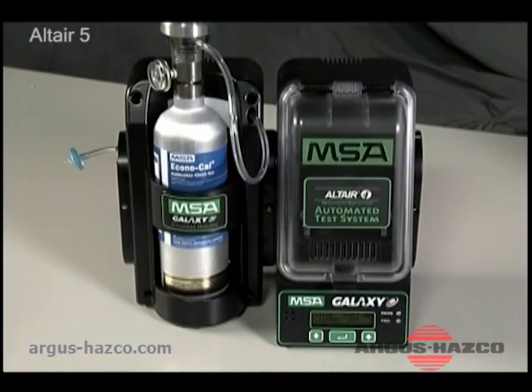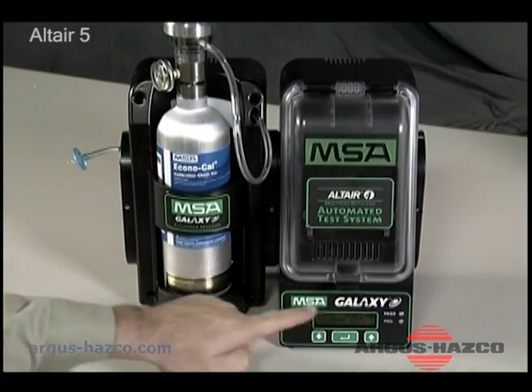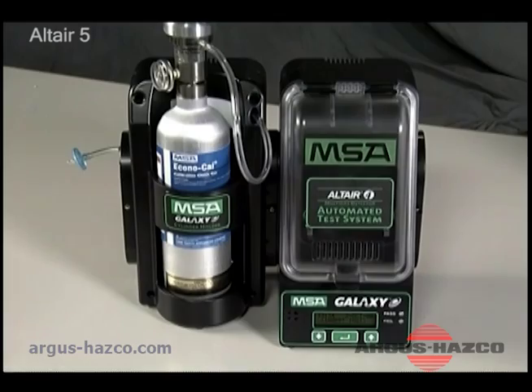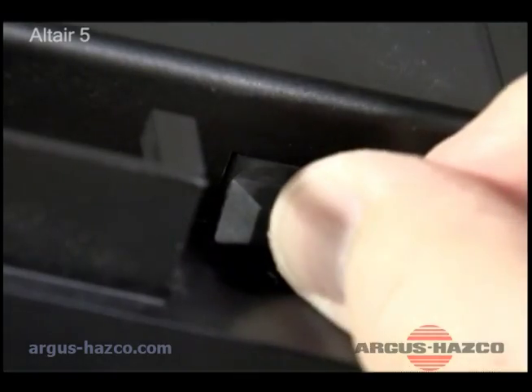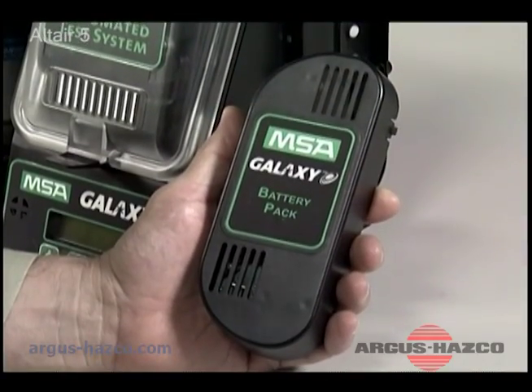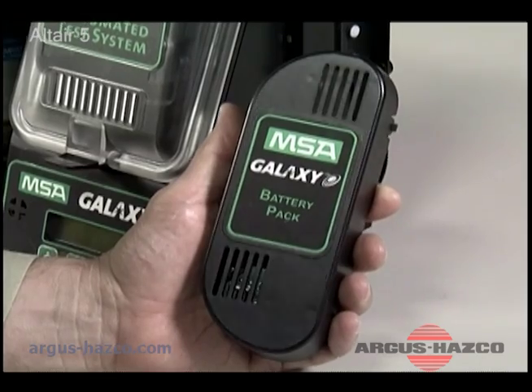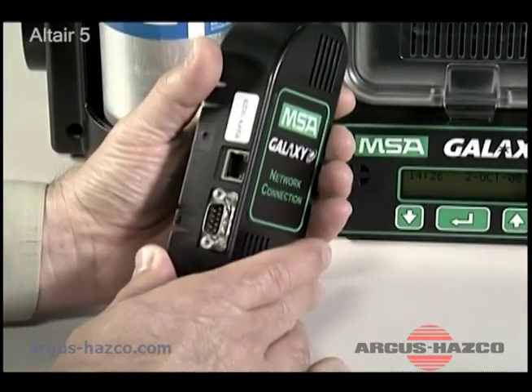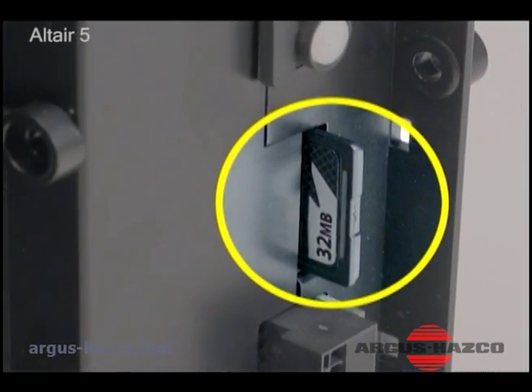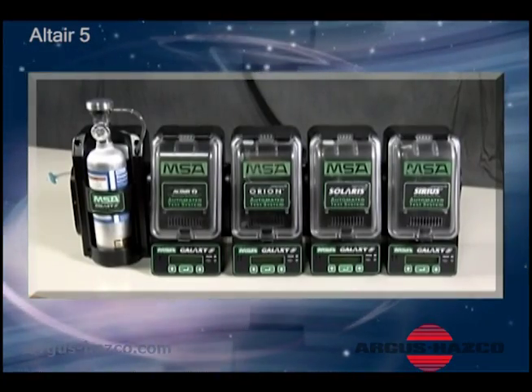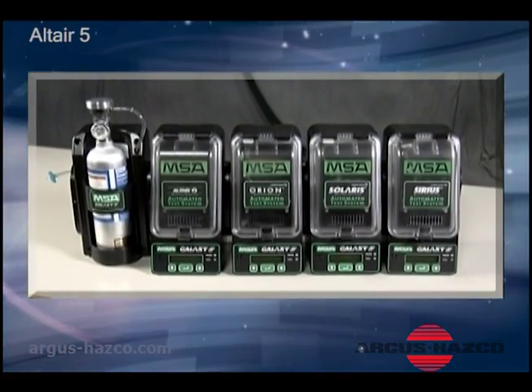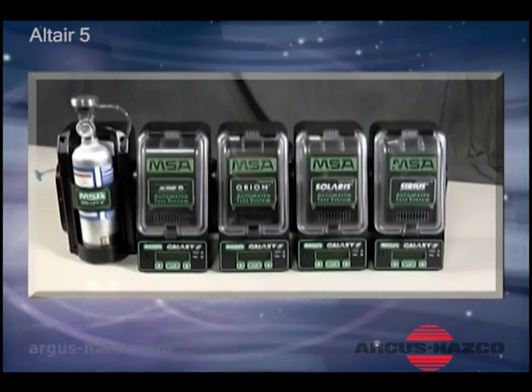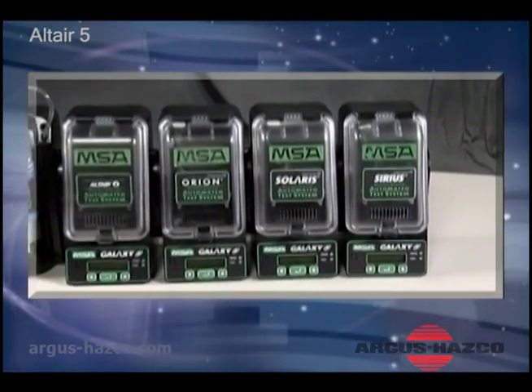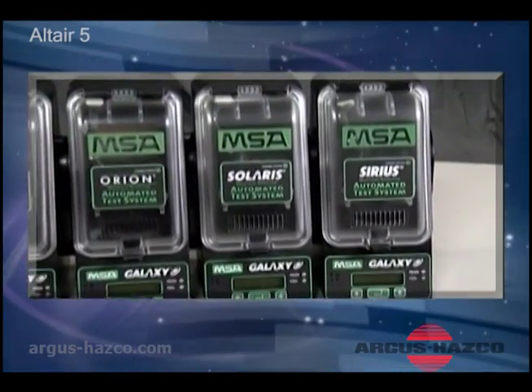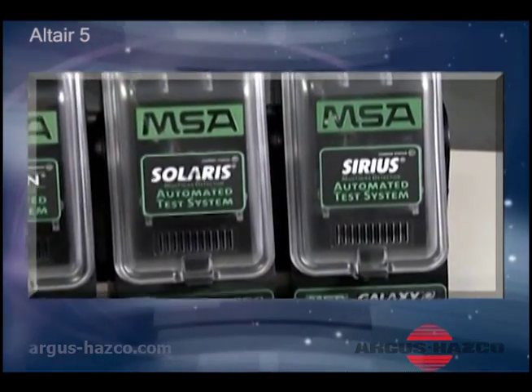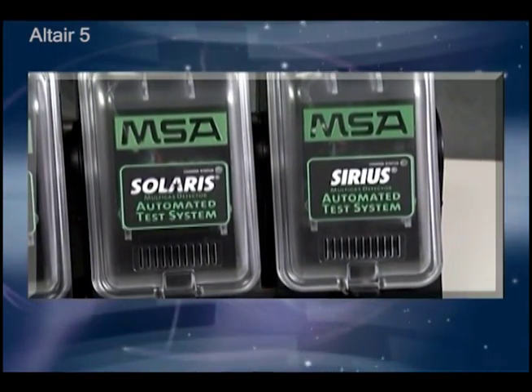The Galaxy automated test system's components are the test stand and AC power module. Optional components are a replaceable battery pack, network interface, and memory card. The Galaxy system is expandable up to 10 test stands with any combination of instruments and up to 3 cylinder holders. When linking 2 or more Galaxy system test stands, only the last unit can accept a memory card.